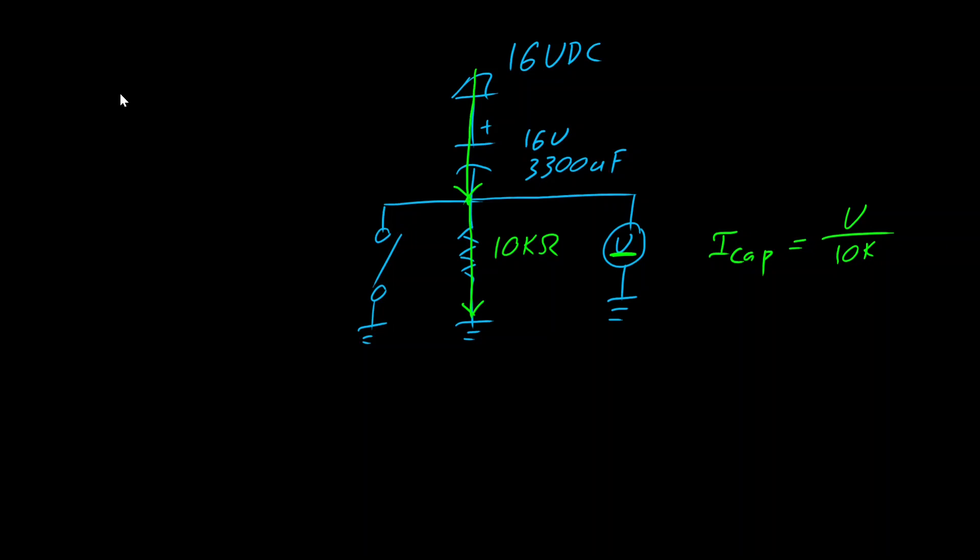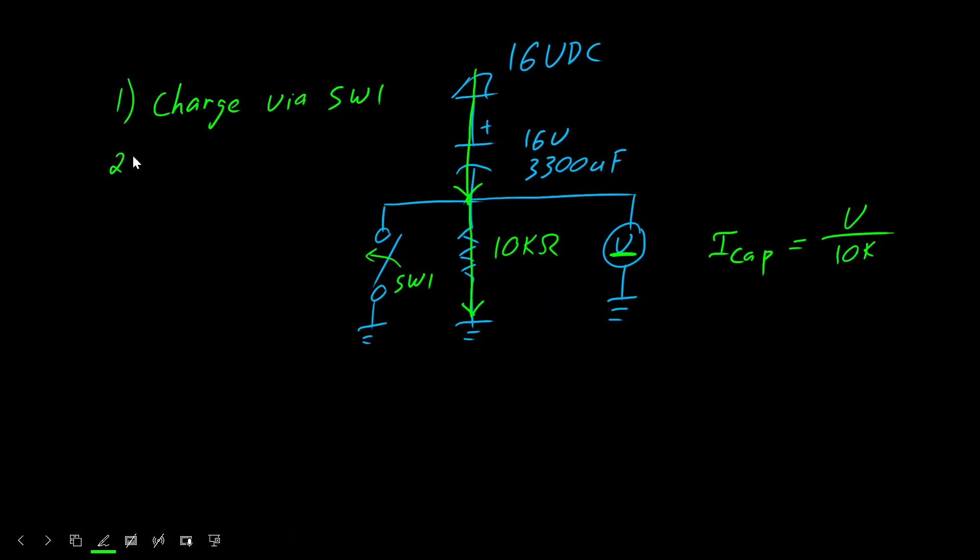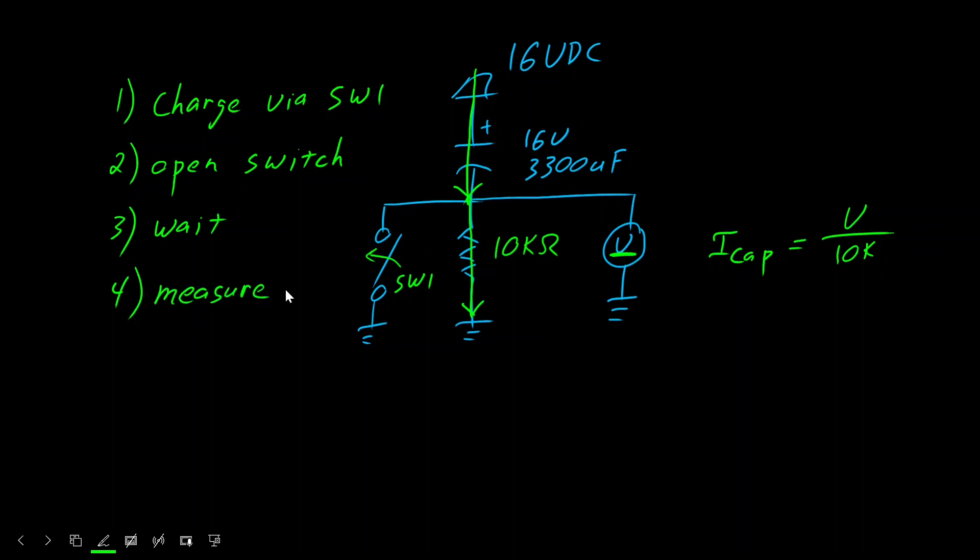Again, multiple steps. We charge the capacitor by closing this switch. We'll call this switch one. The next step, open the switch. We'll want to wait a few minutes for that current to stabilize. And then we measure.